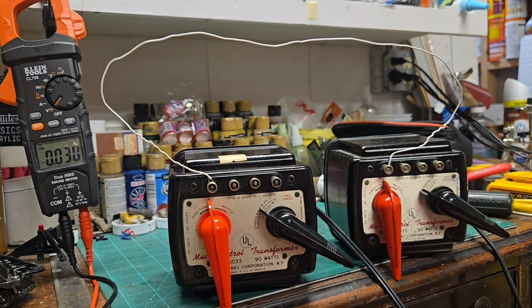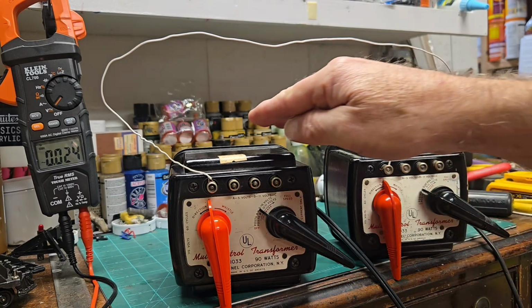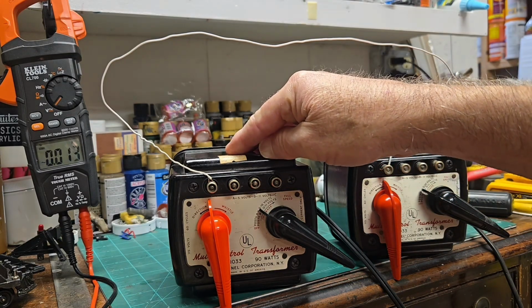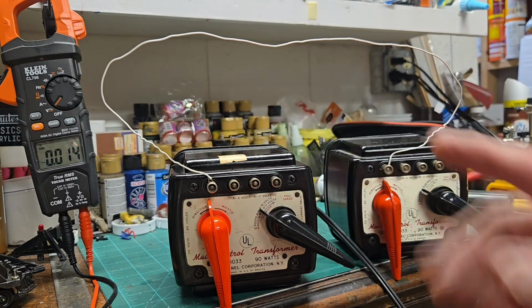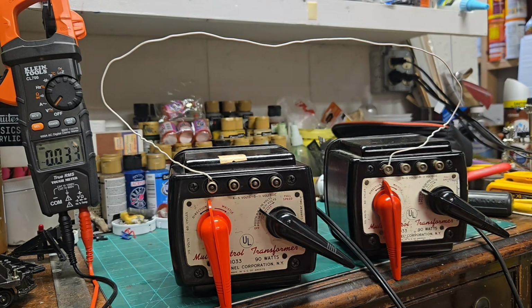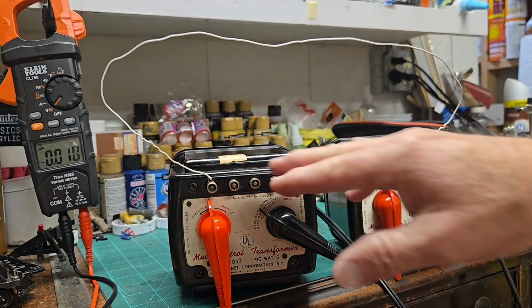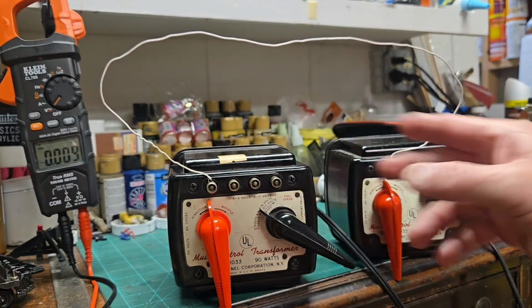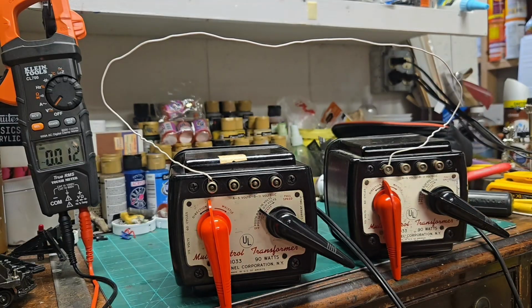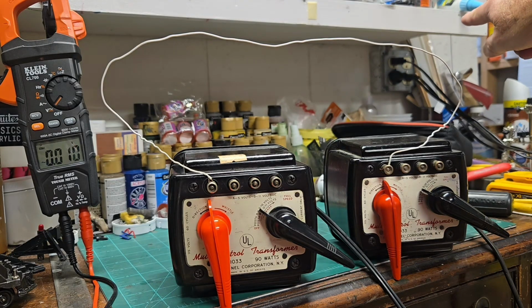That way I can show you how to make sure you can phase your other transformers, especially your post-war style, with your CW80, to ensure that your U terminal on that transformer will always be U and your A will always be A. So the easy way to do that, you can do it two ways. We can switch these two wires around on any one of these transformers and they would be back in phase. Or the preferred method I use is, if you've got these older transformers...